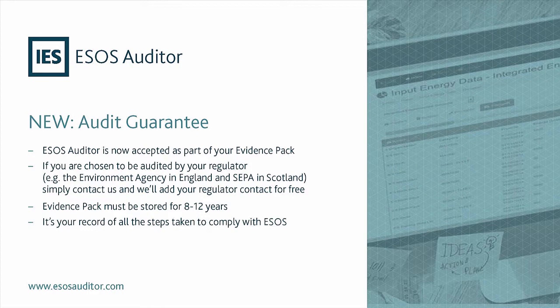Your evidence pack needs to be stored for between 8 to 12 years because it's the current compliance period and the 2 compliance periods after that, and it is your record of all the steps you've taken to comply with ESOS. So it includes things like your total energy consumption calculations and all the evidence to support that, your identified areas of significant energy consumption, your evidence linked to that, and your evidence linked to the audits that you've undertaken, and also your energy saving opportunities that you've identified.